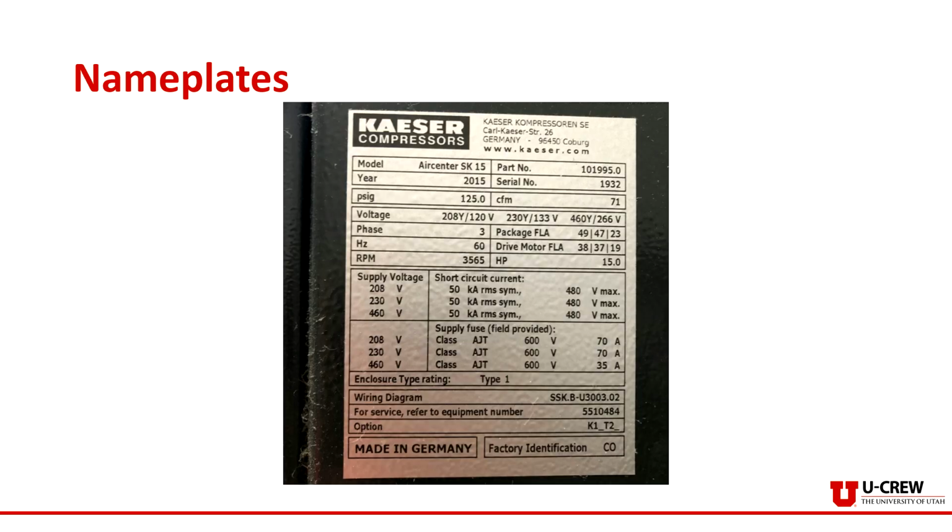Okay, so here's an example of a nameplate. So what can we learn from this? Well, we can see the manufacturer. This is the Kaeser compressor. Over here's the part number or model number. Those are the same thing, and the serial number. You can also usually find some other useful information on these. For example, right below the serial number, you can see that this compressor is rated to a maximum pressure of 125 psi and a maximum airflow rate of 71 cubic feet per minute.